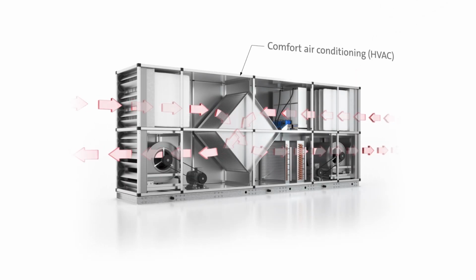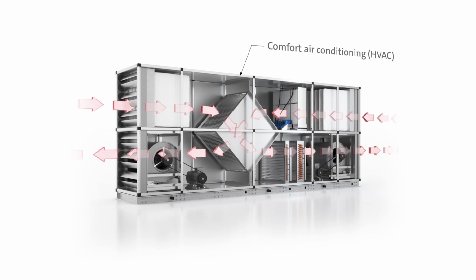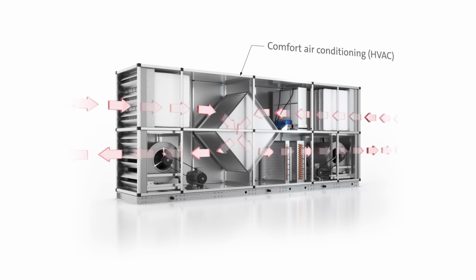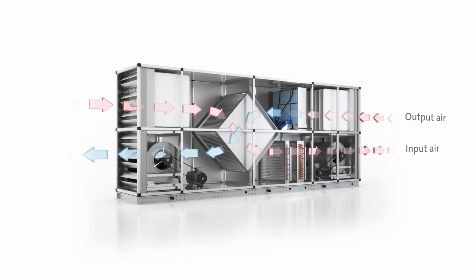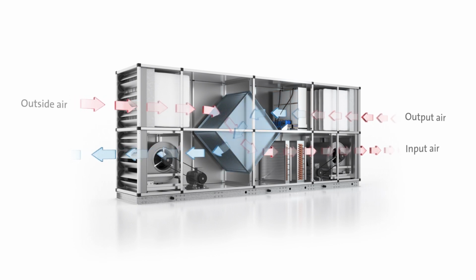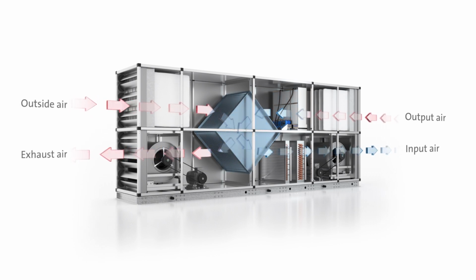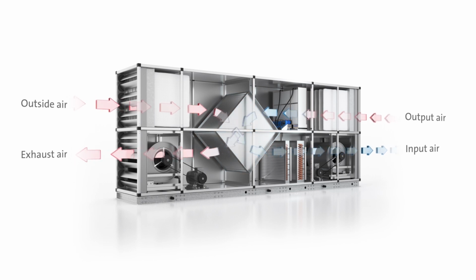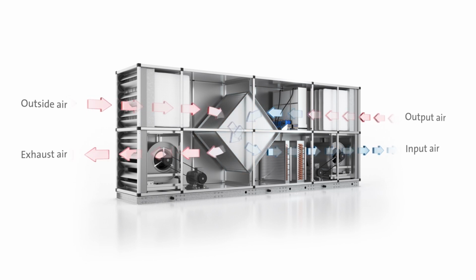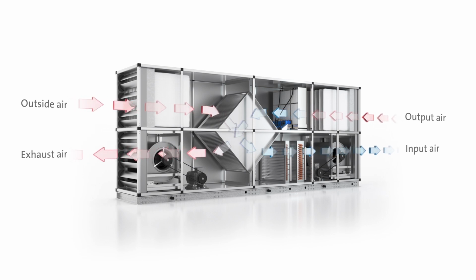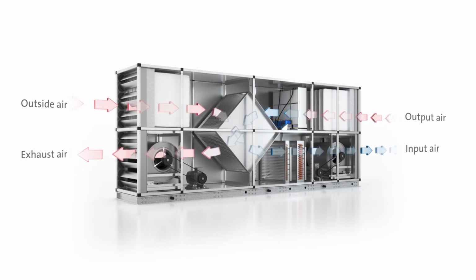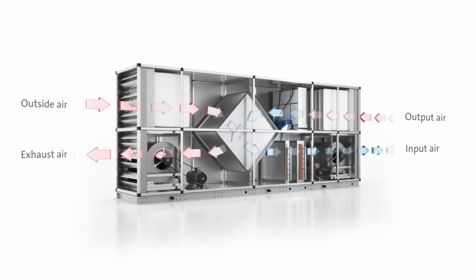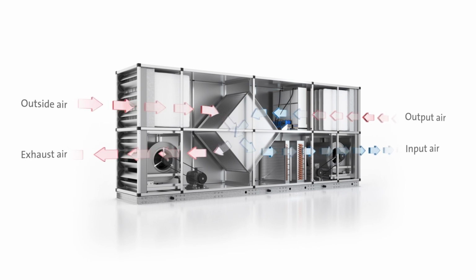In HVAC systems, adiabatic cooling can be used as a cost-effective alternative to conventional mechanical cooling. The exhaust airflow from a room can be cooled by means of an evaporative cooler. A cross-flow heat exchanger is used to cool the air sucked in from outside. Using an evaporative cooler allows to do without a cooling coil, or at least to reduce its size, and therefore its power consumption significantly. If correctly calculated, this leads to significant savings in operating costs.